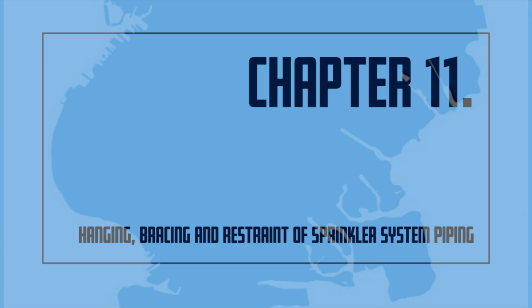Chapter 9 of the NFPA No. 13, 2002 edition describes in great detail the fundamentals of hanger design and installation and should be used as a reference guide for accurate inspection results that will be reported to the owner and the FDNY. There are any number of different deficiencies that may be found during the inspection process.